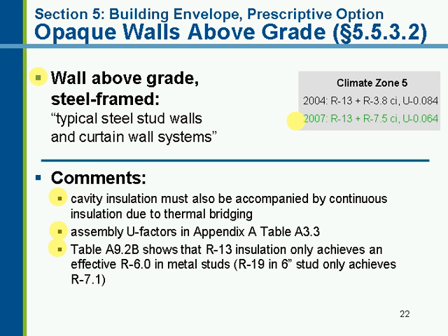So as designers, the point here to take away is to try to minimize the amount of insulation you put between metal studs. Go with a smaller stud, smaller Z-channel, and as much continuous insulation as you can. You get much more effective thermal performance if you do that.